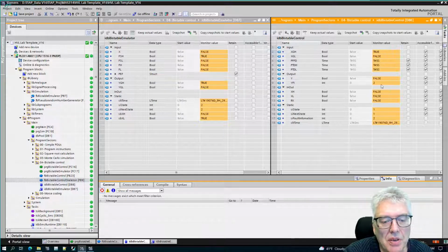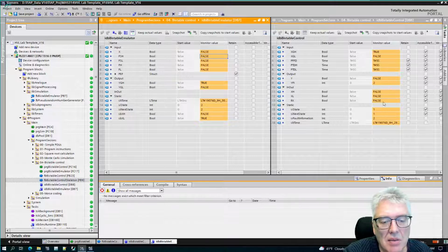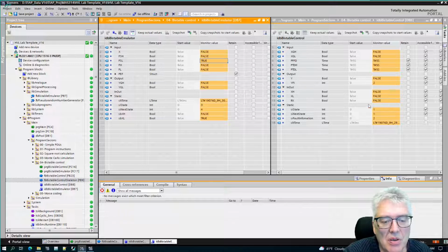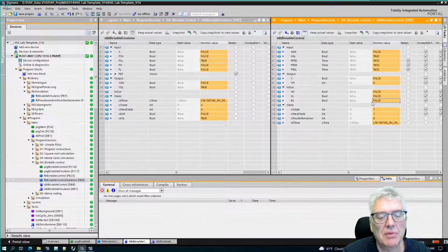So what I can do is try to reset this one. That's this one. Try to make it down. Operate. Yes, I can switch this one off. It doesn't reset. That's the reason why: the error is still there. The feedback was false, not correct. So now we can just toggle. So now I'm back in state 1. And if I now try to reset this one, now there's no feedback error. It's okay. Moves to 0.